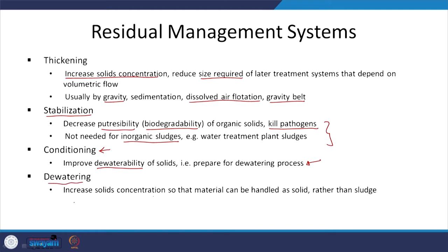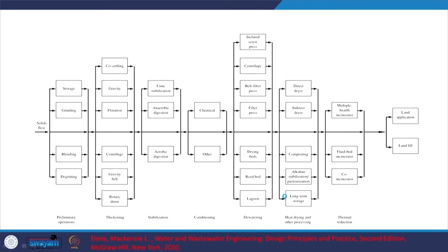The final step is dewatering: increase solids concentration so that we handle it as a solid rather than as a sludge, and then disposal to landfill or apply it to soil. Looking at the bigger picture, depending upon the kind of solids coming in, some preliminary options include blending or grinding. For thickening, we have gravity, flotation, and gravity belt. These days people are also looking at rotary drum or belt press.